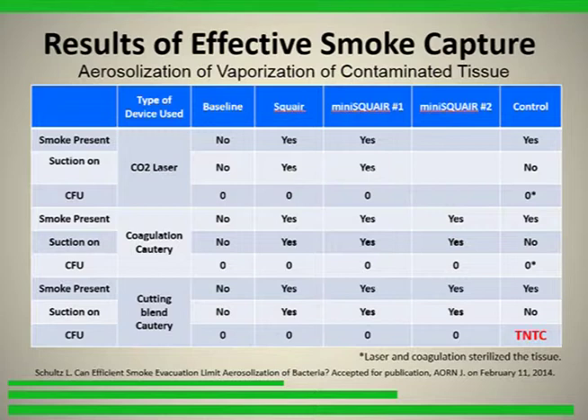Now, if you look at the other columns, notably Squair and miniSQUAIR, repeated times 2, take a look. In this case, suction was on, the miniSQUAIR was working, connected to a standard smoke evacuator device, and we repeated the same sequence. Again, we have no colonies formed with CO2, no colonies formed with coagulation current, and no colonies present with the blended current. In other words, effective smoke evacuation in this experimental model resulted in no aerosolization of bacteria.